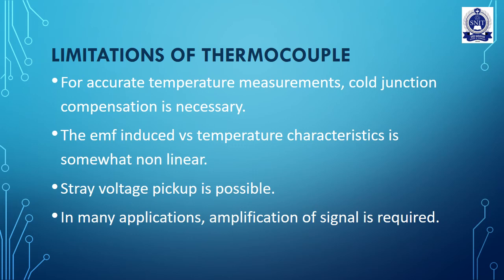Certain limitations include: for accurate temperature measurements, cold junction compensation is necessary. The EMF induced versus temperature characteristic is somewhat non-linear. Stray voltage pickup is possible, and in many applications amplification of the signal is required, which adds extra work.